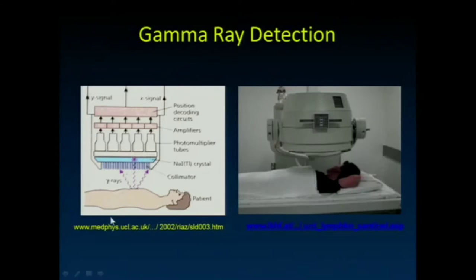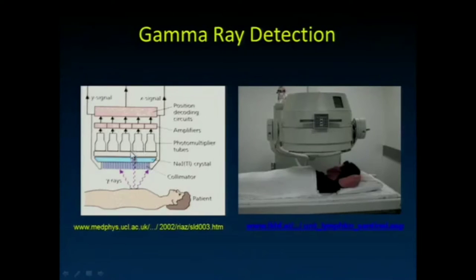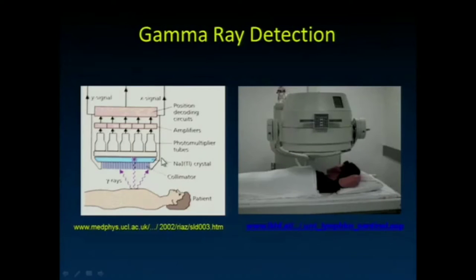Events occur far enough apart in space and time that I can detect each one individually. By detecting the amount of light seen by adjacent photomultiplier tubes, I can interpolate where the event occurred. The tube closest to the event sees the majority of the light; surrounding tubes see smaller percentages. The sum of the light detected by all of them tells me the energy of the interaction. So in nuclear medicine imaging, I retain time, position, and energy information.